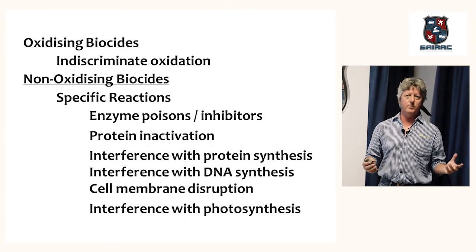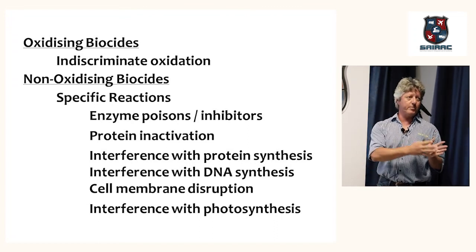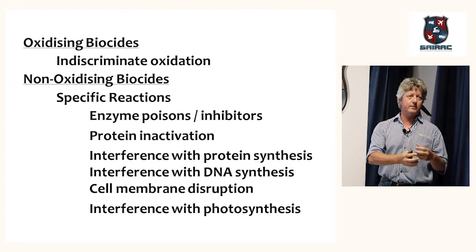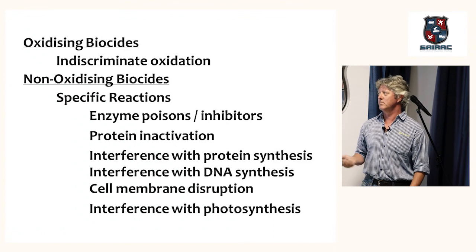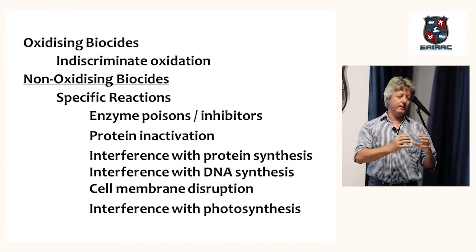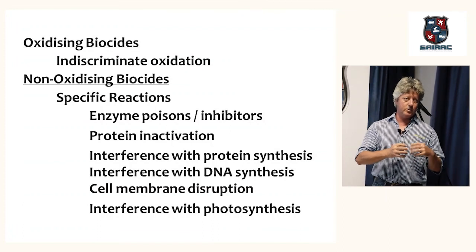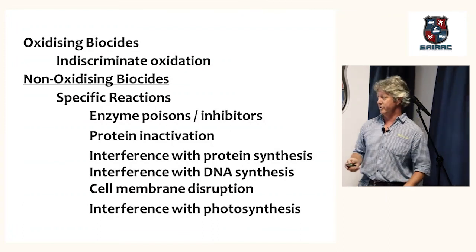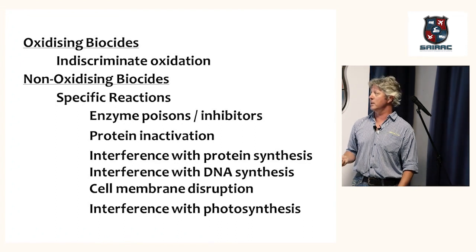Every living organism has enzymes which facilitate life, and some of these non-oxidizing biocides interrupt the enzyme, they destroy the enzyme to such an extent that that part of the life cycle can't happen and your bacteria will die. Protein inactivation, enzymes are proteins, so it's basically the same thing. Interference with protein synthesis, interference with DNA synthesis, and then cell membrane disruption, which means that the cell membrane is disrupted in such a way that excess water might flow in, causing the cell to burst. It can actually close it off a little bit, which means that no nutrients can actually enter the cell. So these are the different ways that non-oxidizing biocides work. And interference with photosynthesis, which is applicable to algae.